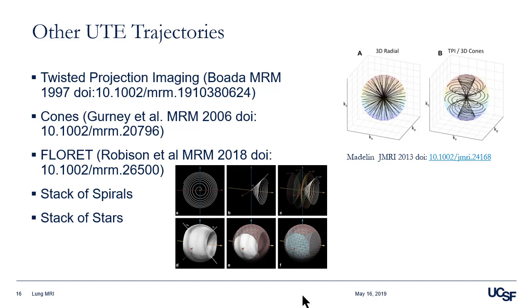You do have options within both UTE and ZTE pulse sequence trajectories. I've shown examples of both radial and cones or twisted projection imaging type sequences. There's nice recent work from Jim Pipe and Ryan Robeson using the floret trajectory, which is a cool option. You can also get quite good imaging results with stack of spirals or stack of stars trajectories done in a center-out fashion.